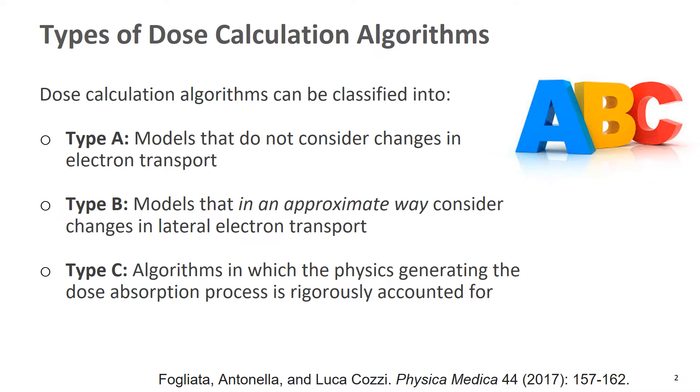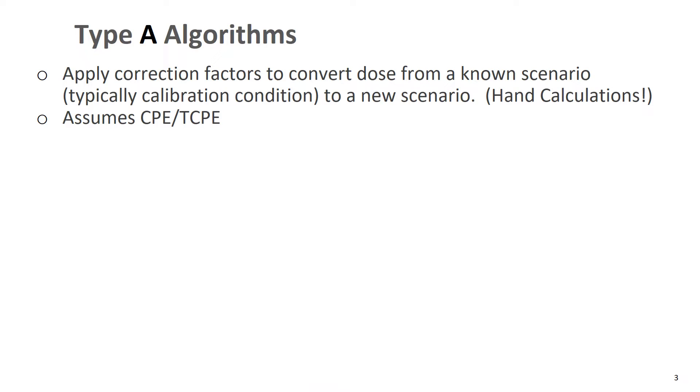We'll get into a little more detail about each of these. So let's start with type A algorithms. These are those that apply a series of correction factors to convert dose from a known scenario, which is typically the calibration condition, to a new scenario.